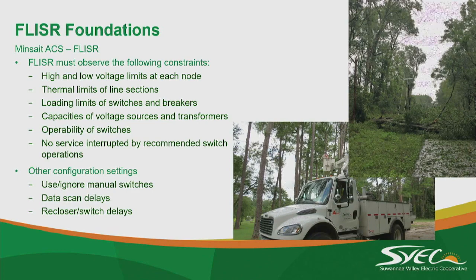Based on our communications, we can change our data scan. So if your system is slower than you thought, you can back out this data scan to give your relays time to report in, and collect all the data before you make a decision. You can also leave a delay from the time you sent a command to make sure you get confirmation the device opened or closed.